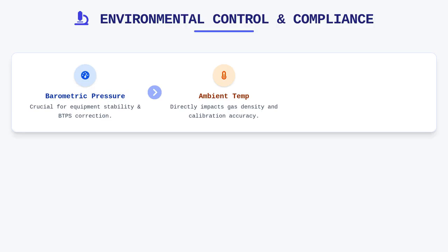Managing external variables, such as barometric pressure and ambient temperature, is essential for maintaining the stability of your equipment. Most modern software compensates for these fluctuations automatically, but you must ensure that your laboratory environment remains within the specified range for accurate BTPS correction.